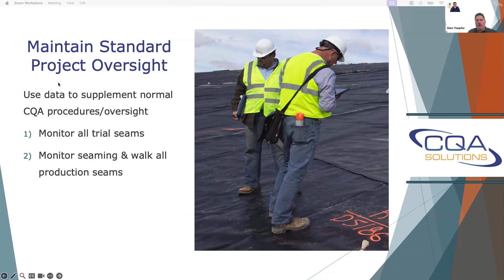You really need to have, or it's suggested anyway, that the requirements of the ASTM be verified. CQA personnel really need to monitor the machine setup of the data recorders and verify any parameters. If the data is being used for evaluation, timeliness is critical, and data must not be allowed to be hidden. I'd also say: refrain from altering protocols.